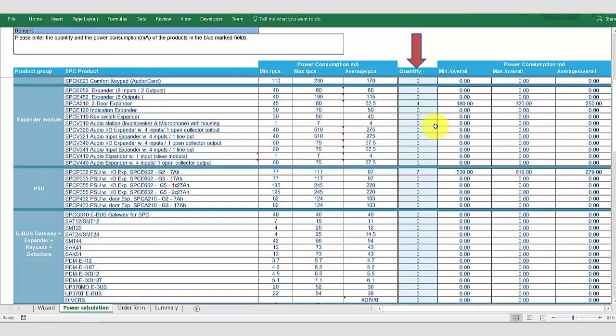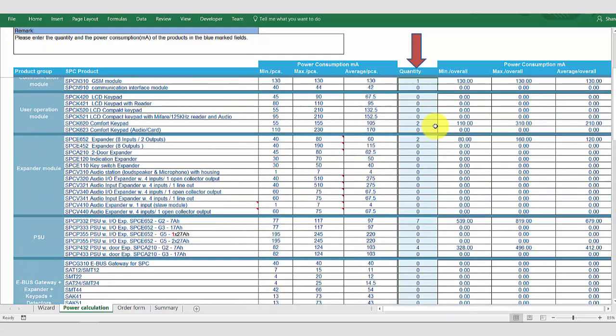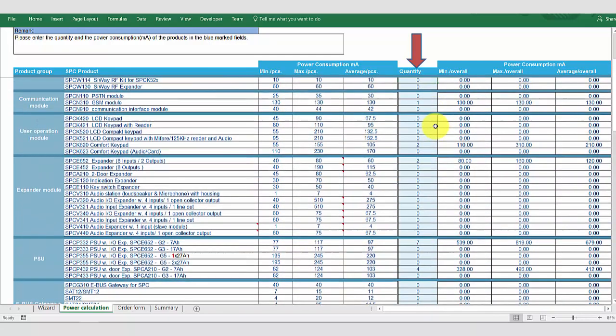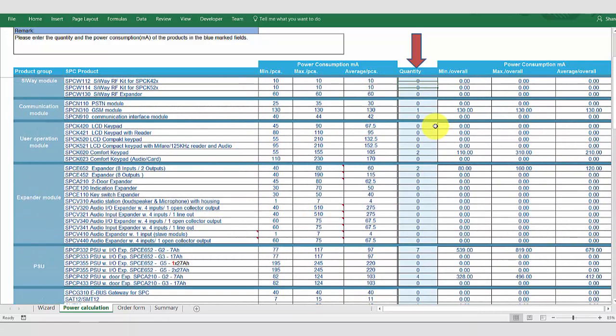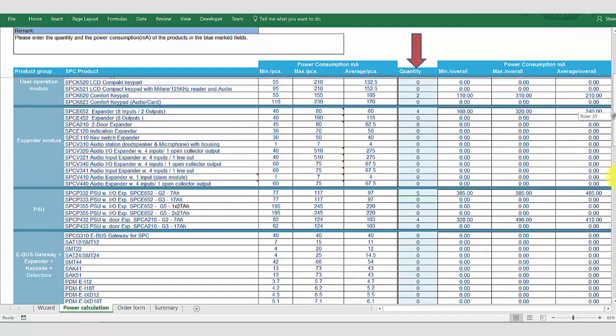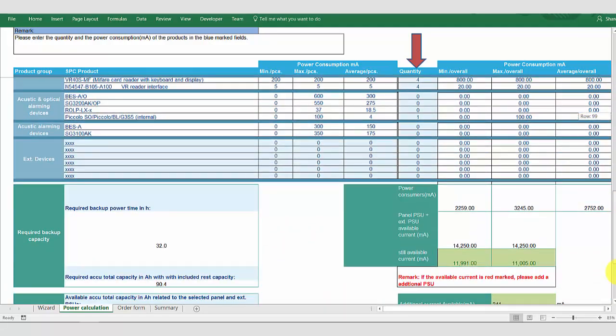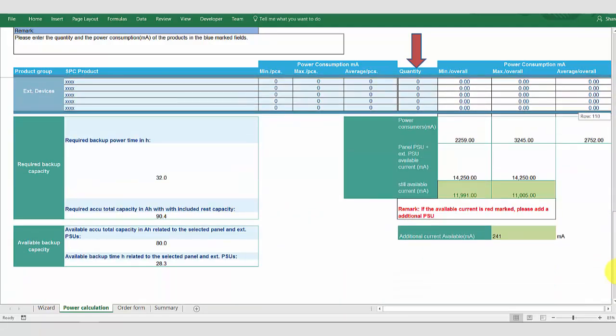So, what I can do now is I'm going to change the door controllers to the power supply variant door controllers. And I will increase the number of standard expanders we have and reduce the power supply variants. So, let's just check what this does for our power calculations. And we are within limits.